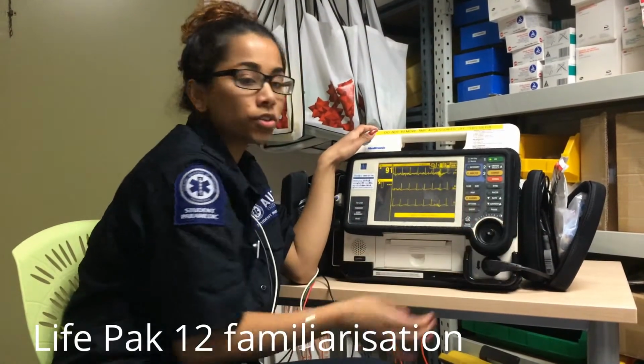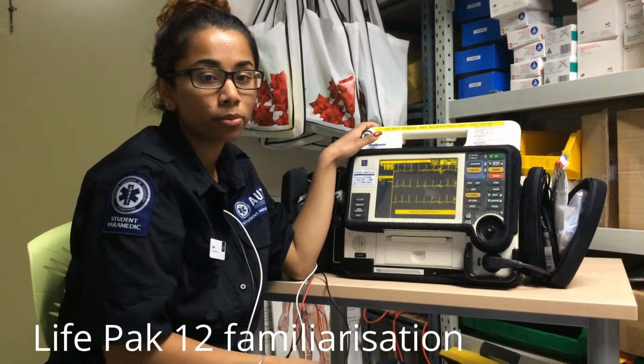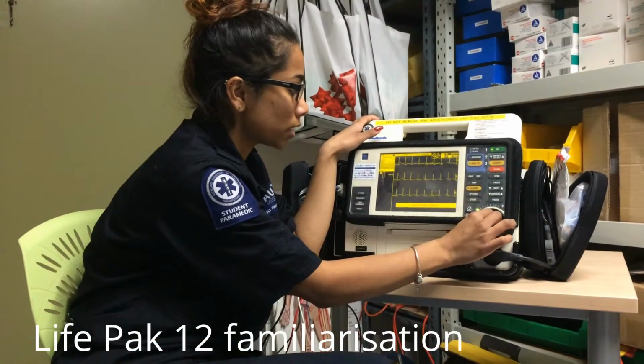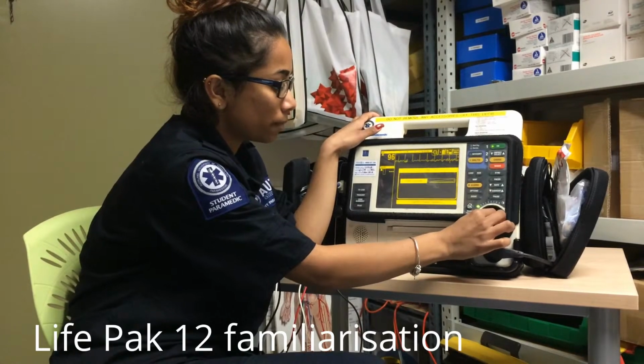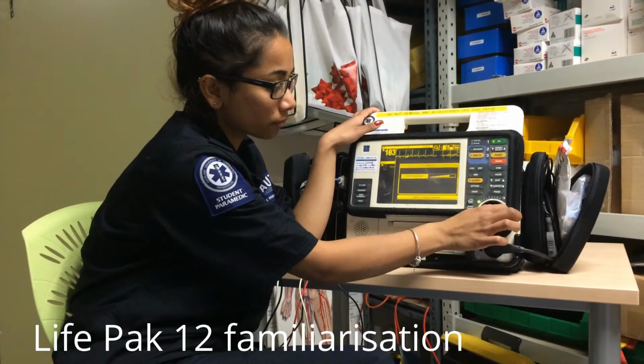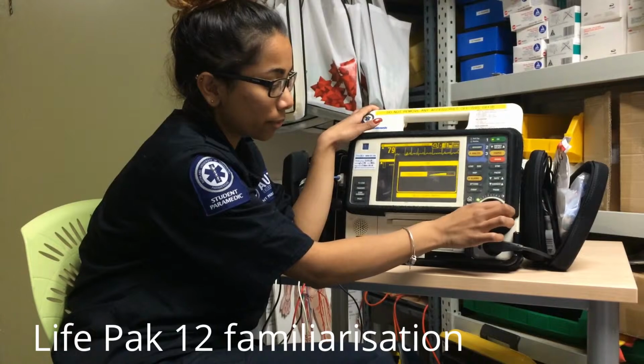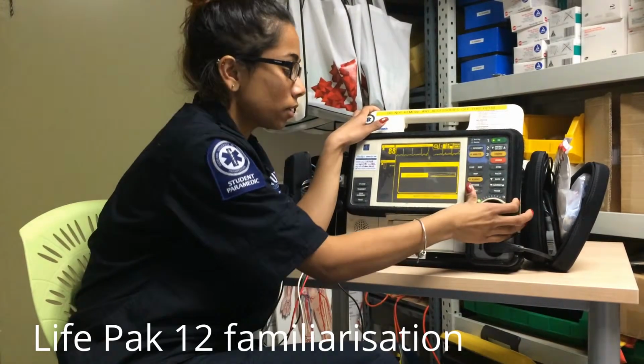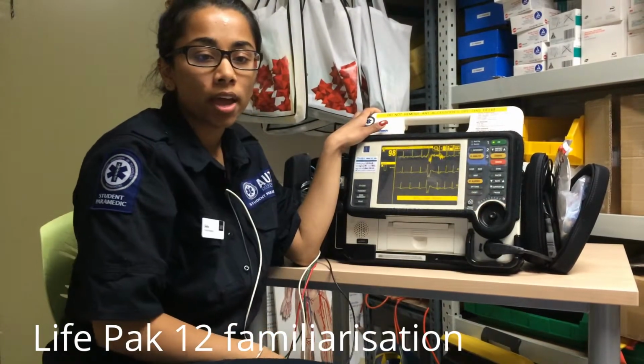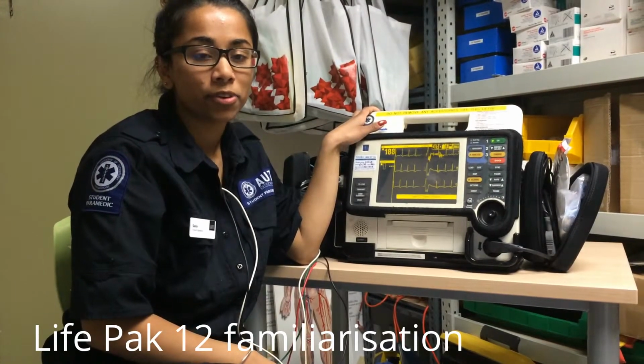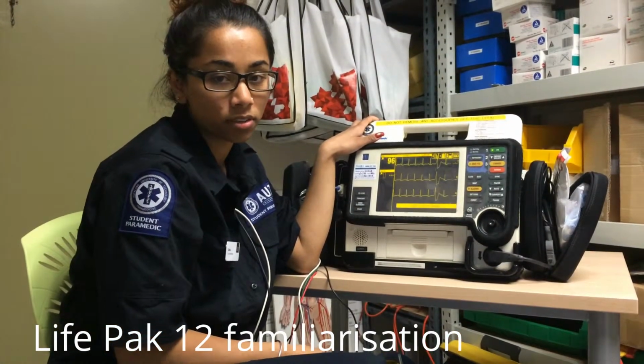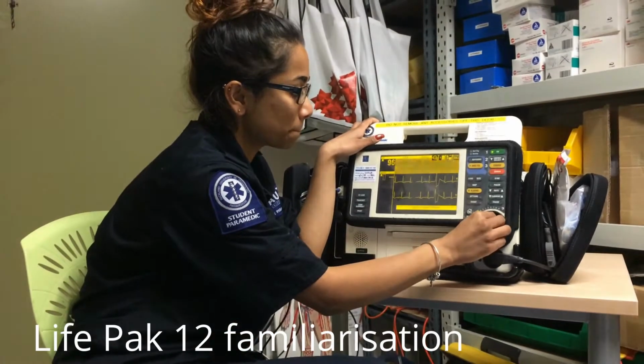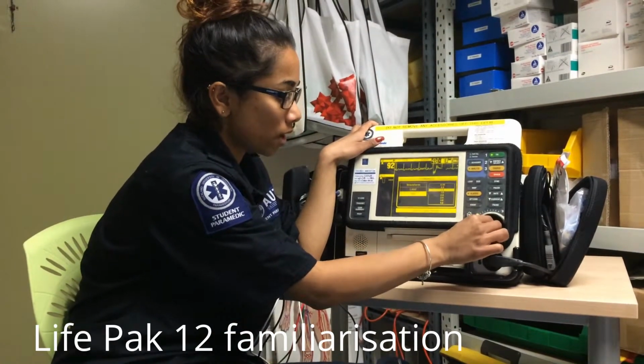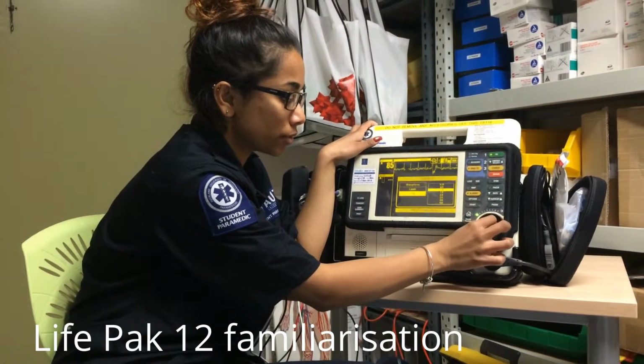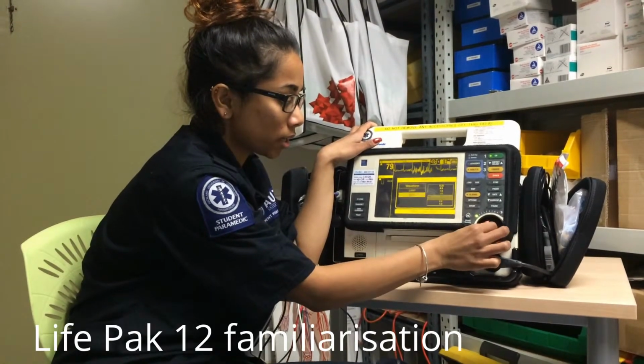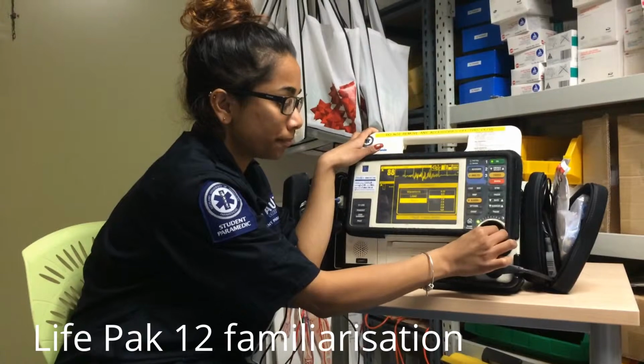And if you want a specific lead, you can then also change that and have a look at that as well. So also to adjust the QRS volume, you can go over to the heart rate section, which is located here, and you can either raise the volume or lower the volume, like so. And also, if you want to change the amplitude of the ECG size, you can select the channel, go to size, and you can choose from 1.0 to 4.0, as well as you can also choose 0.25.